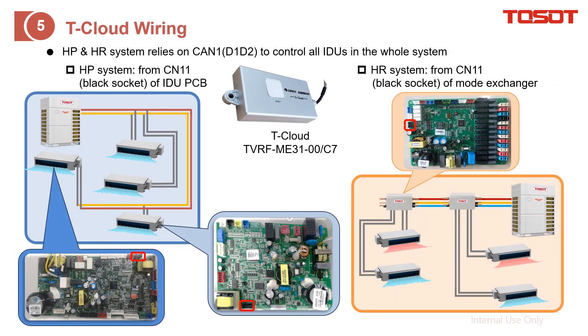We also support controlling the VRF system from your smartphone. We call it T-Cloud, which relies on the T-Cloud module. Where to install it? It is on the HP system — you need to plug it into CN11 of the indoor unit, shown here for the old PCB and for the other kind of PCB. As for the HR system, it is also CN11, but this time we make it into a mode exchanger, also called a branch box.